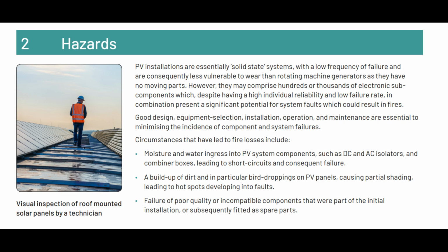Secondly, a buildup of dirt, especially bird droppings, can cause partial shading, leading to hotspots and faults. Lastly, the failure of poor quality or incompatible components, either from the initial installation or subsequent replacements, is a significant risk.